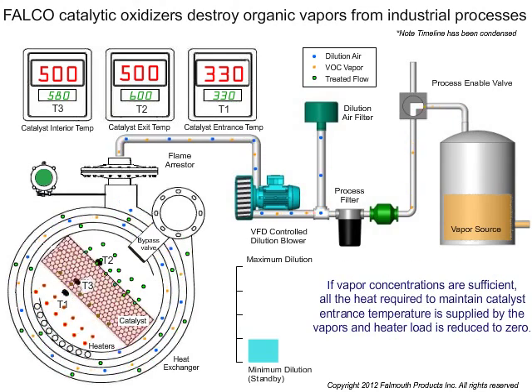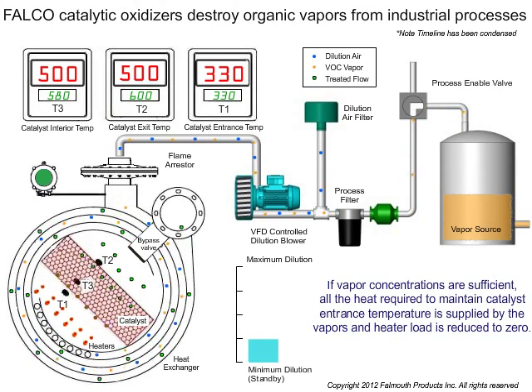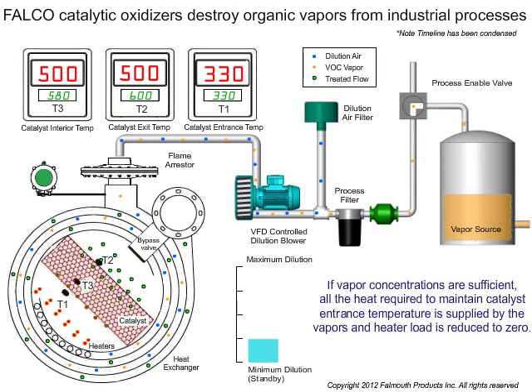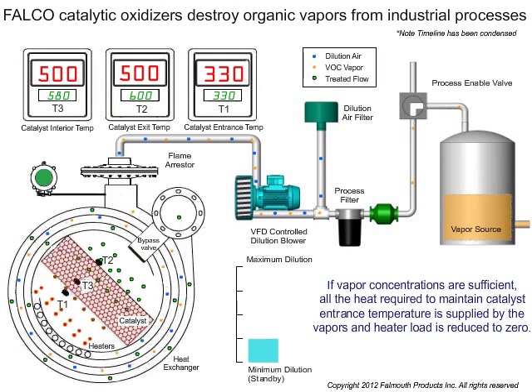If vapor concentrations are sufficient, all the heat required to maintain catalyst entrance temperature is supplied by the vapors and the heater load is reduced to zero.